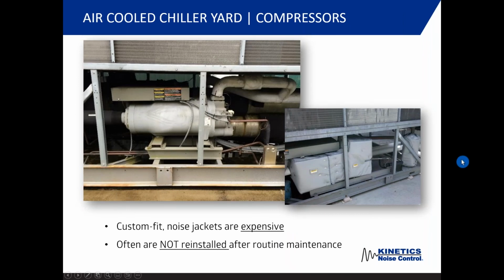So one thing left, we talked about it in the beginning. We talked about the custom fit wraps. There's nothing wrong with custom fit wraps, okay? They take care of the tonal noise, the function of one item, the noise of the chiller. So that is needed. What you look at though is there's some custom fit wraps with special clasps and straps and all kinds of things, and they look great when they're installed.